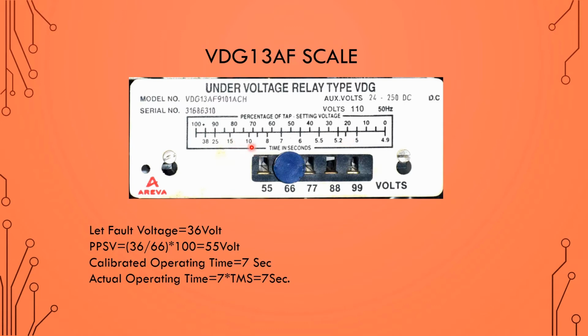And this is the IDMT characteristic, that means inverse characteristic. So now I will show how to calculate the actual operating time without operating the relay for a particular value of fault parameter. So here the fault parameter is the voltage. So let the fault voltage we are giving be 36 volt. In this way we should plot in the observation table how to calculate for different values of fault voltage. We should calculate the trip time before operating the relay. That we will tell during the observation.